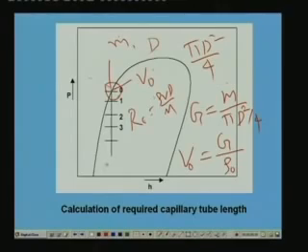Once you know the Reynolds number, you can find out friction factor, because friction factor is equal to 0.32 Reynolds number to the power of minus 0.25. Okay, so this is the friction factor at the inlet. So likewise, I find out all the required quantities at this point. Okay, then what I do is I assume suitable temperature drop, as I have already explained to you. Once you assume the suitable temperature drop, that means you come to the point 1.